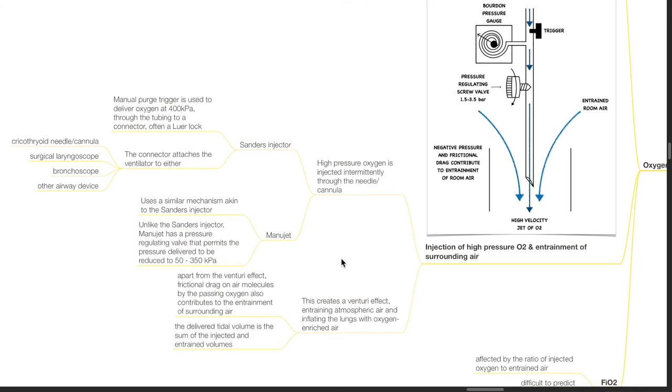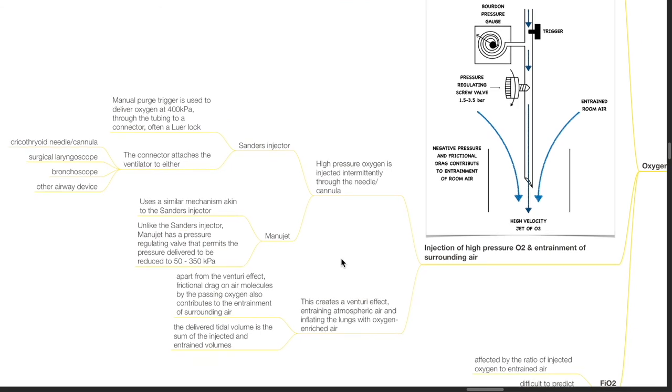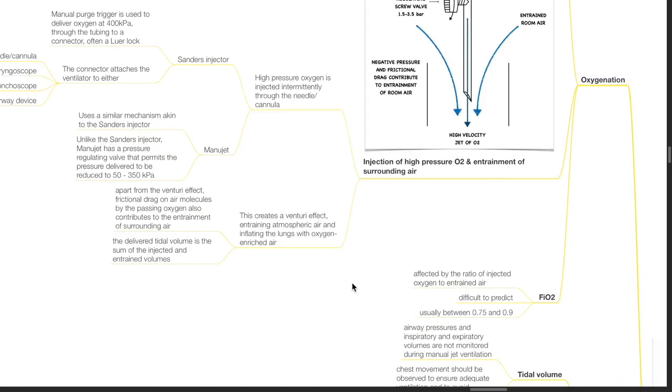Injection of high pressure oxygen creates a Venturi effect, entraining atmospheric air and inflating the lungs with oxygen-enriched air. Apart from the Venturi effect, frictional drag on air molecules by the passing oxygen also contributes to entrainment of surrounding air. The delivered tidal volume is the sum of injected and entrained volumes of gases. FiO2 is affected by the ratio of injected oxygen to entrained air and is difficult to predict.